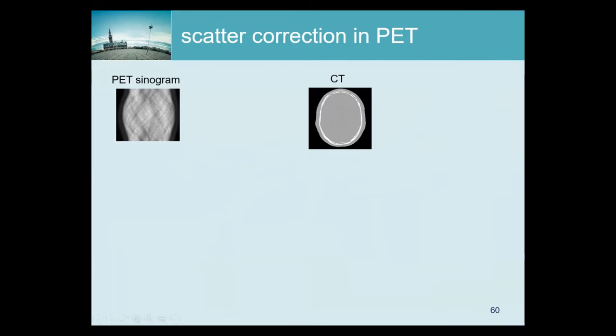For scatter correction in PET, people first tried to use energy-based scatter correction, but it didn't work very well. At that time, that was with BGO and poor energy resolution. It could be that now, with the much better energy resolution we have in our PET scanners, energy-based methods might work, but I don't think many people are trying because we have established scatter correction methods that are based on scatter simulation.